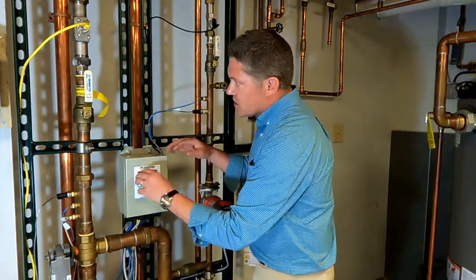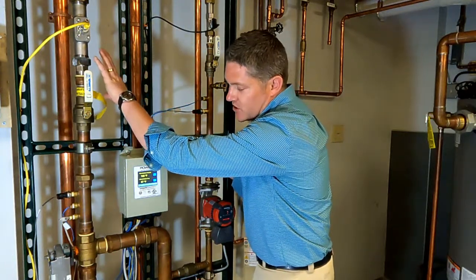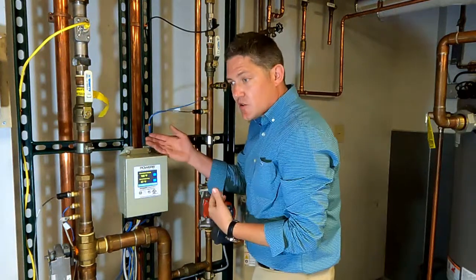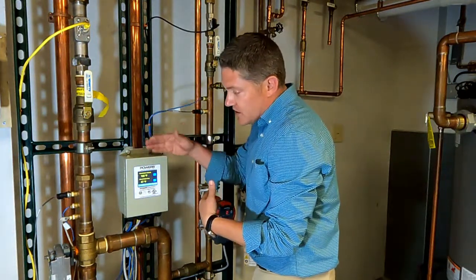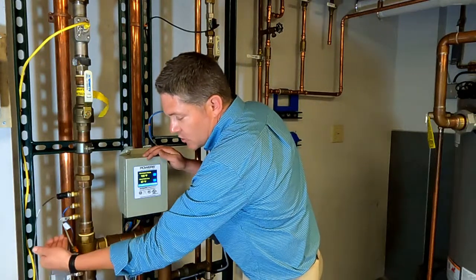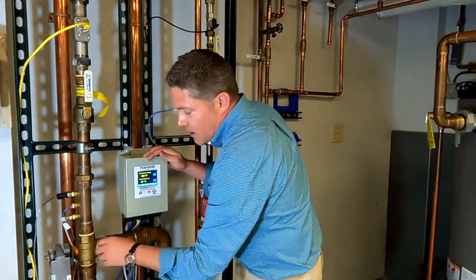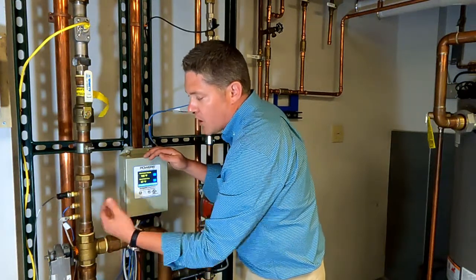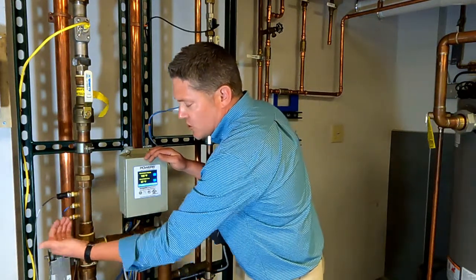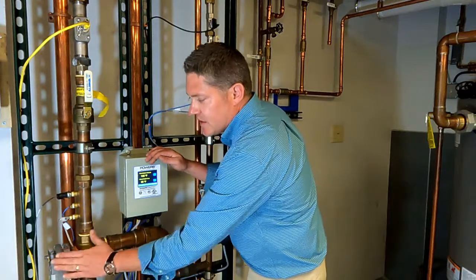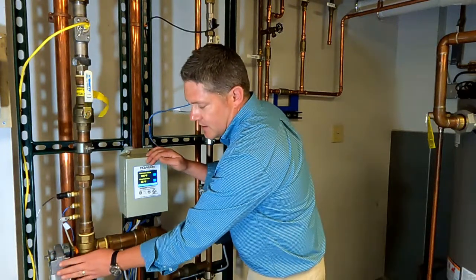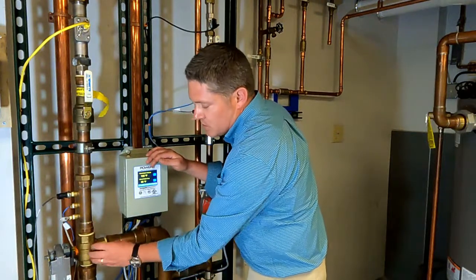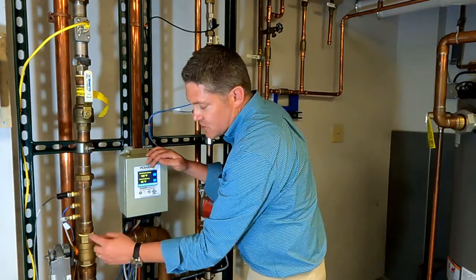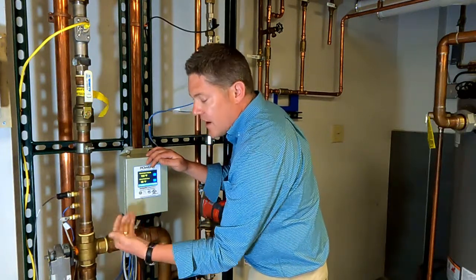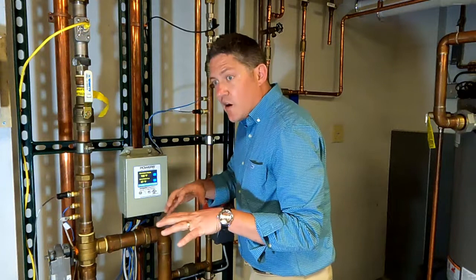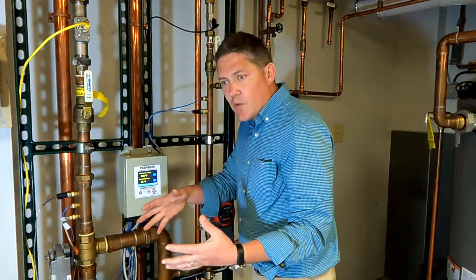So the way this works is that the temperature sensor on your mixed outlet senses that the temperature has risen too high above your set point. It's going to tell that actuator to move the stem on the 3-port ball valve, allow a little bit more cold water in than hot water to bring that temperature back down to set point. It's always kind of adjusting, tick, tick, tick. That digital actuator is in constant motion.